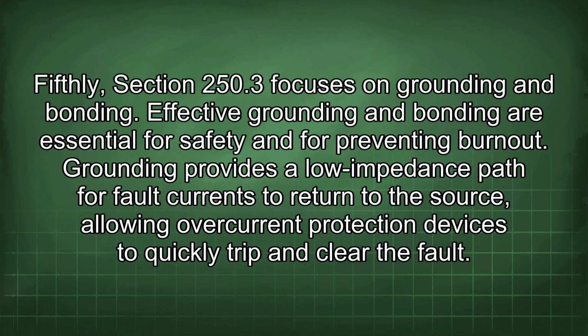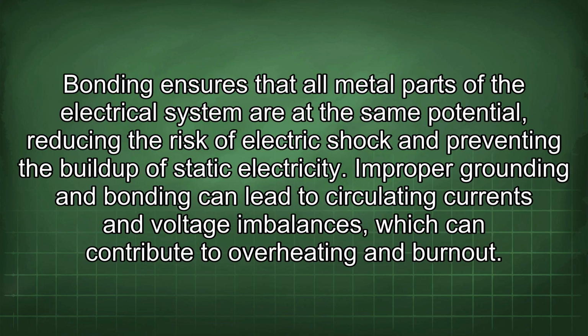Fifthly, Section 250.3 focuses on grounding and bonding. Effective grounding and bonding are essential for safety and for preventing burnout. Grounding provides a low impedance path for fault currents to return to the source, allowing overcurrent protection devices to quickly trip and clear the fault. Bonding ensures that all metal parts of the electrical system are at the same potential, reducing the risk of electric shock and preventing the buildup of static electricity. Improper grounding and bonding can lead to circulating currents and voltage imbalances, which can contribute to overheating and burnout.